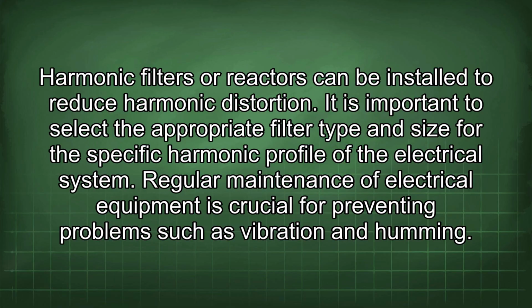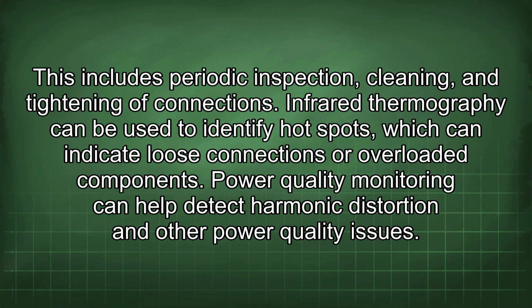Regular maintenance of electrical equipment is crucial for preventing problems such as vibration and humming. This includes periodic inspection, cleaning, and tightening of connections. Infrared thermography can be used to identify hot spots, which can indicate loose connections or overloaded components. Power quality monitoring can help detect harmonic distortion and other power quality issues.